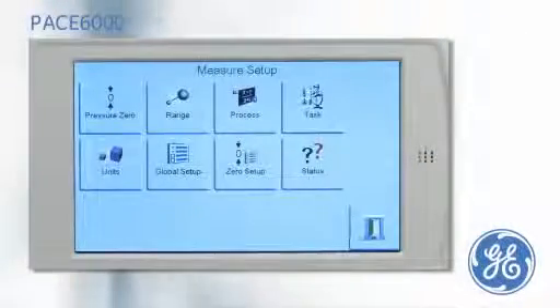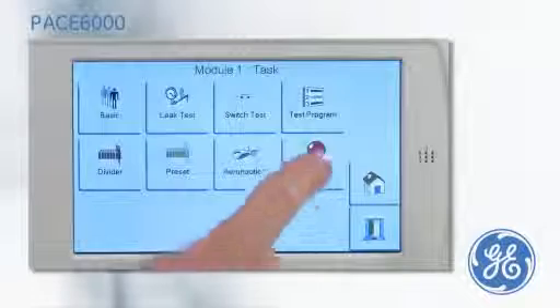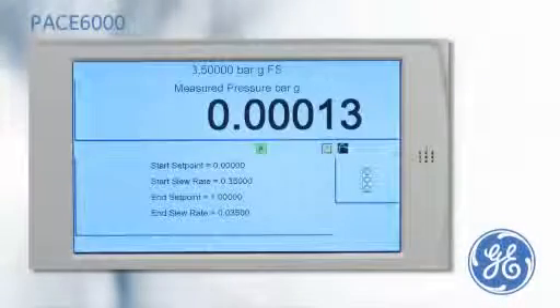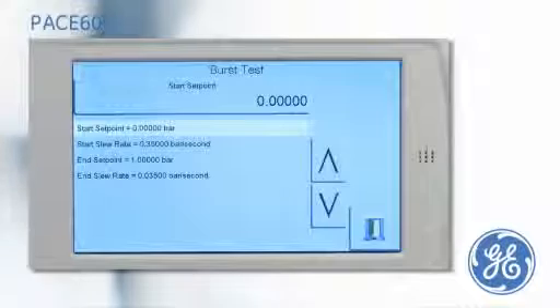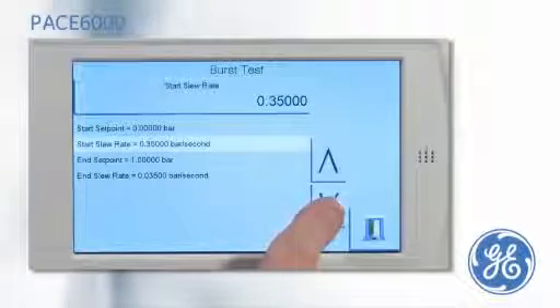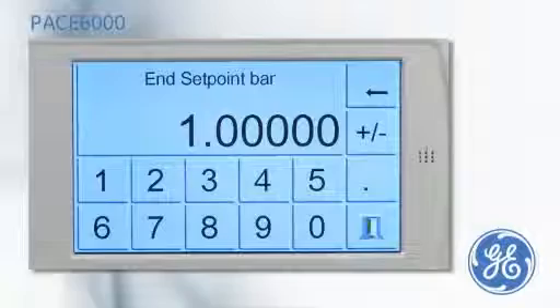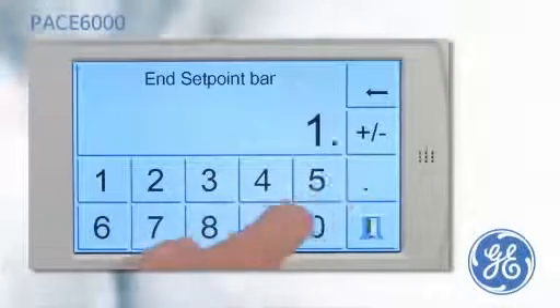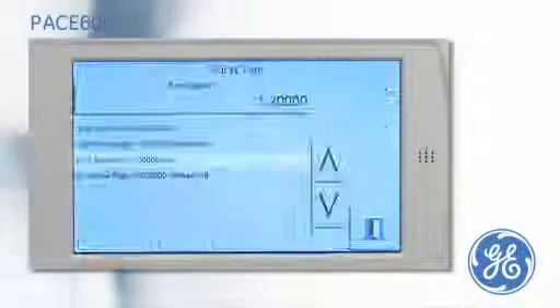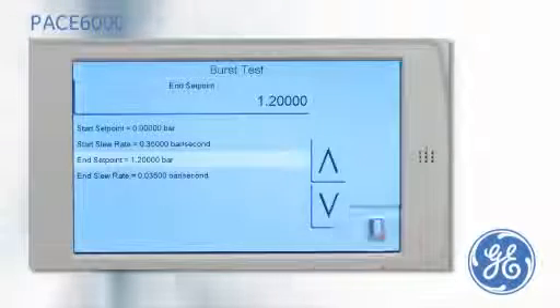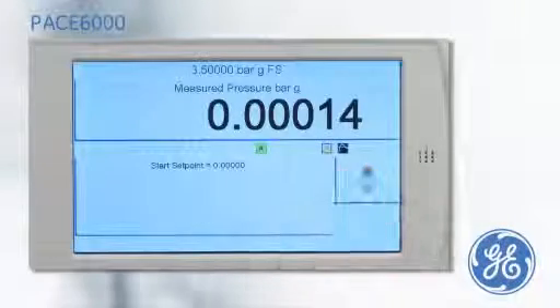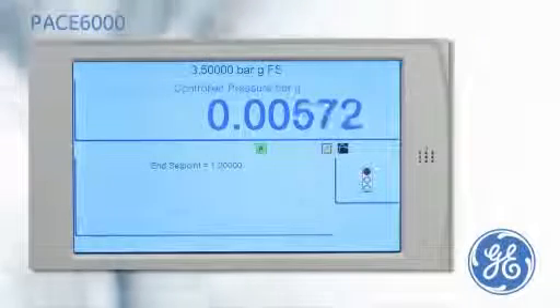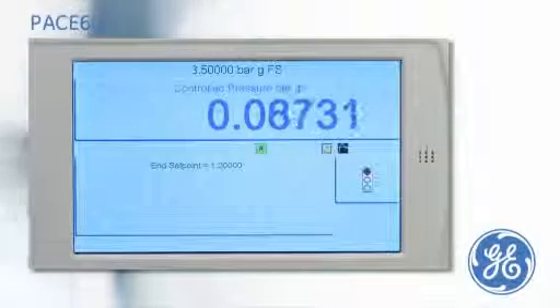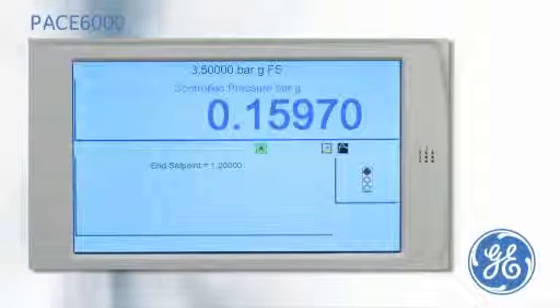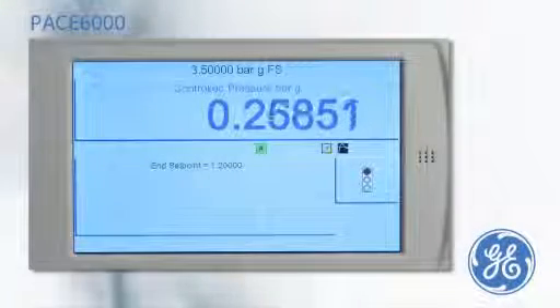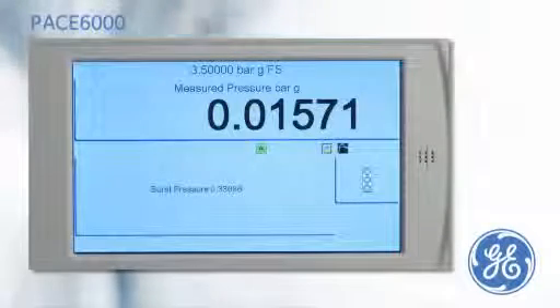For rupture point testing, the PACE has an optional burst test task. From the menu, the start set point pressure is set. The end set point of 1.2 bar is entered, which is higher than the expected burst. The slew rate can be changed if required. The burst test is started by pressing the green traffic light. An increasing pressure is applied until the pressure is released by the burst disc rupturing. The PACE captures and displays the burst point of the device.